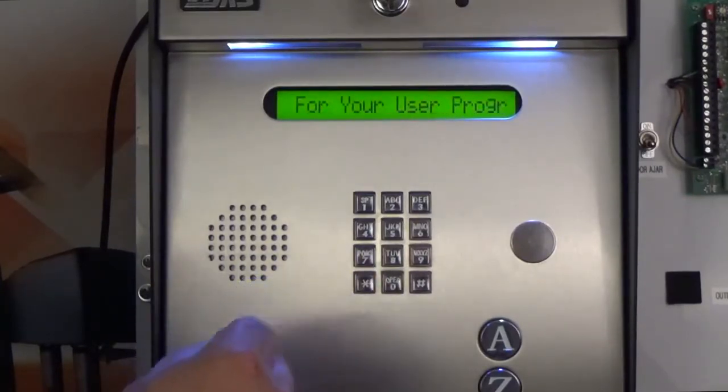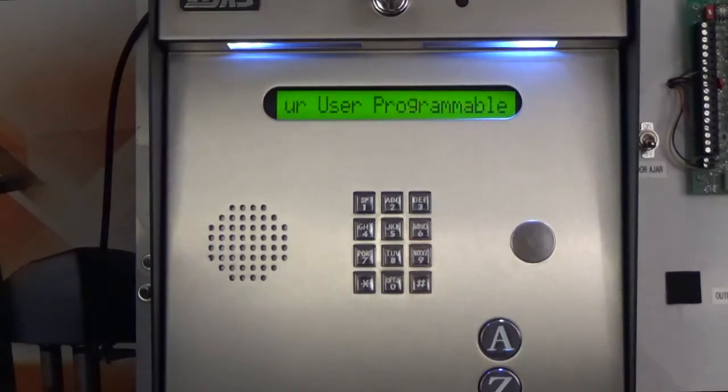If the test fails, go ahead and refer to the matrix chart in the manual to check continuity between the RS232 terminal strip and the end of the serial cable on the DB9 connector.